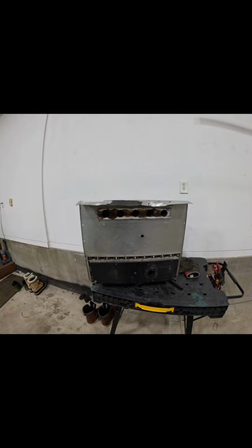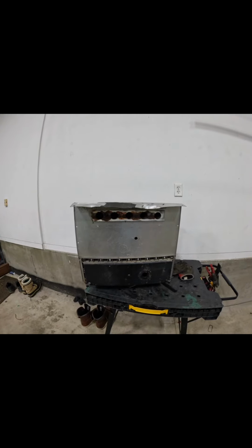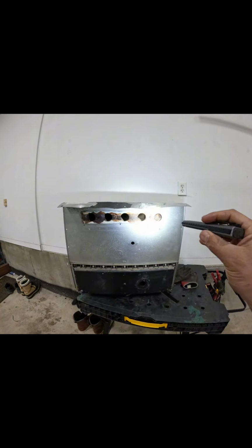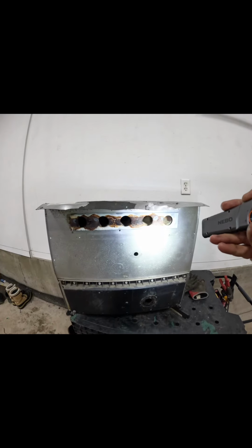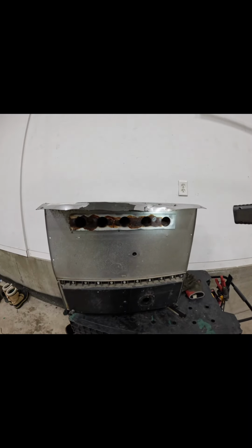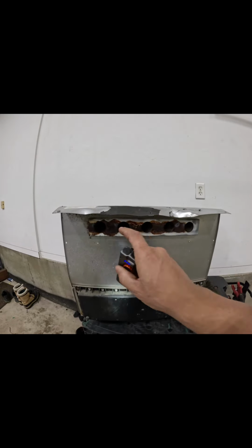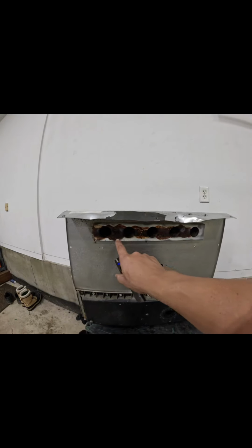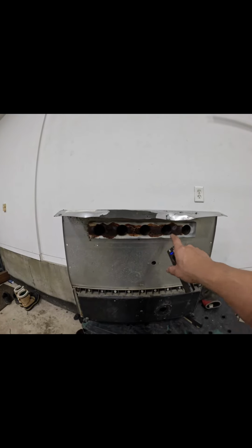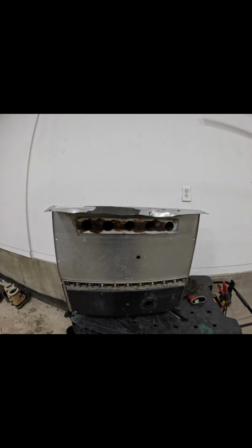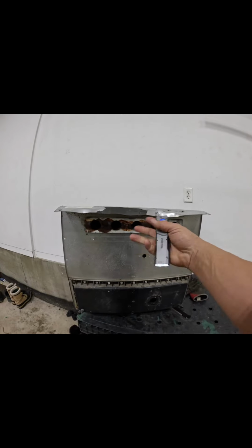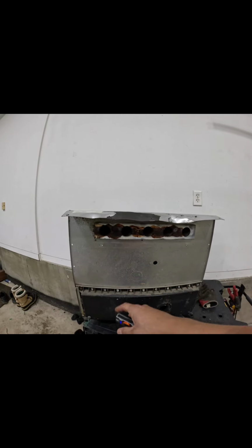Let's talk about the anatomy of the heat exchanger a little bit. This is where the flame is - oh, that light is super bright. This is where the flame goes in, right here. You can figure each tube is roughly 20,000 BTU. This unit is a 100,000 BTU furnace, and you can see that adds up pretty much.